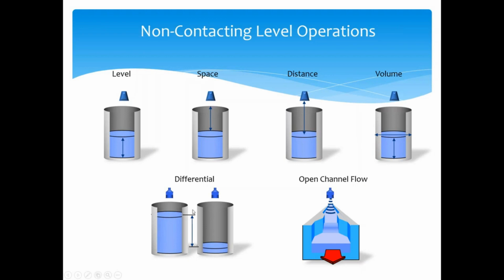We'll see differential quite regularly, specifically if we're doing differential across a bar screen, like at the headworks of a wastewater plant. You want to know when that screen is getting clogged. We can do the differential on either side of the screen, bring that back into a single transmitter, and alarm or relay upon that value. And then you can also use ultrasonic or radar for open channel flow. And we'll talk a little bit more later in the presentation about why you would specifically want to use ultrasonic for an open channel flow application.